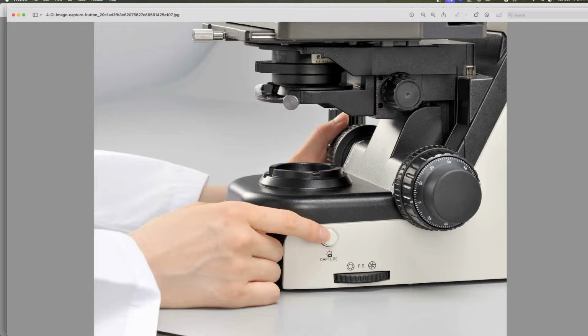So if your light source is dodgy for some reason, like you have a cheap LED and you can see the LED elements, or if the filament in the bulb is failing or has dark or light spots on it, you would see that if you didn't set up your microscope for Koehler illumination.